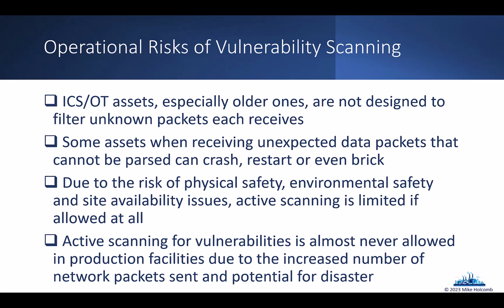Now, why we can't just take a Nessus scanner and plug it into the OT network and start scanning is especially in older environments, older devices like controllers, PLCs, and HMIs and RTUs. The older ones would receive packets that they didn't understand. They would just choke and die. Sometimes the machine might reboot itself, or sometimes it would crash, or it might even brick, so you physically have to replace the system, the asset.